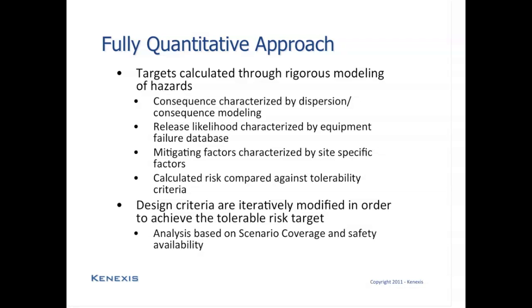After analyzing these figures, we'll look at the mitigating factors based on the site. And some of the mitigating factors will include ignition probabilities, again, based on the type of equipment that is being used and the ways that personnel interact with the equipment. The personnel interaction with the equipment will also define things like what is the frequency or the probability of human beings being exposed to these hazards, and also being able to respond to these hazards if they see them occurring or if they respond to personal monitors or general alarms.